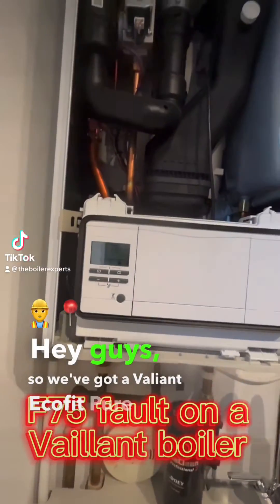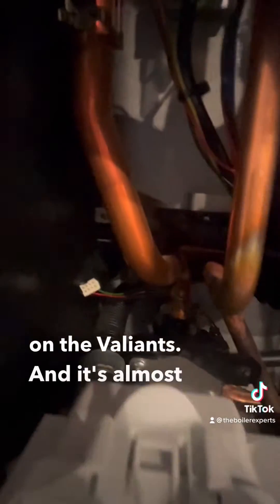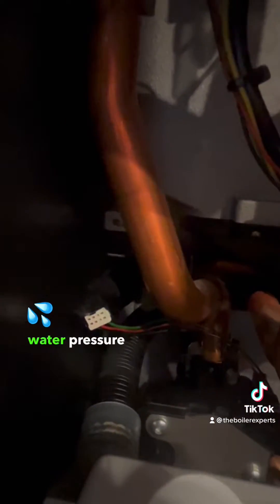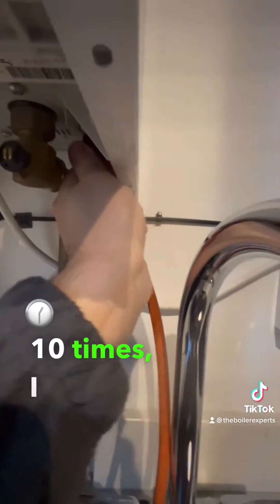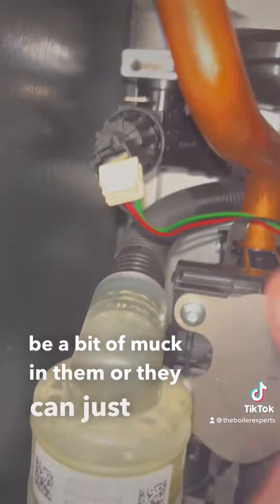We've got a Vaillant Eco Fit Pure here with an F75 fault — a very common fault on the Vaillants. It's almost always these low water pressure sensors. Don't get me wrong, it can be the pump and other circulation issues, but nine out of ten times I end up replacing these low water pressure sensors. They can either have a bit of muck in them or they could just go faulty.